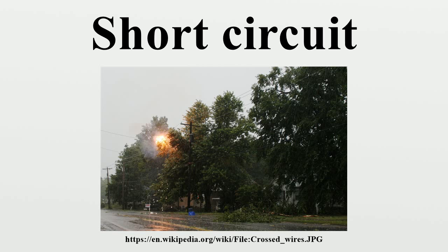Wire gauges specified in building and electrical codes are chosen to ensure safe operation in conjunction with the overload protection. An overcurrent protection device must be rated to safely interrupt the maximum prospective short-circuit current. In an improper installation, the overcurrent from a short circuit may cause ohmic heating of the circuit parts with poor conductivity. Such overheating is a common cause of fires.